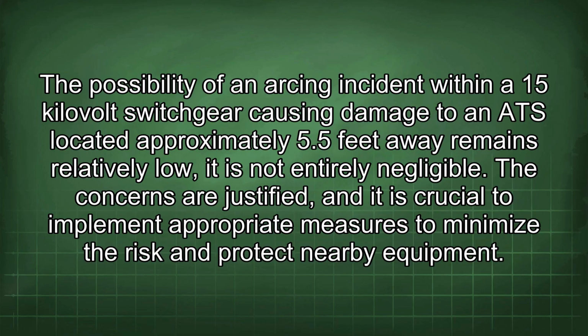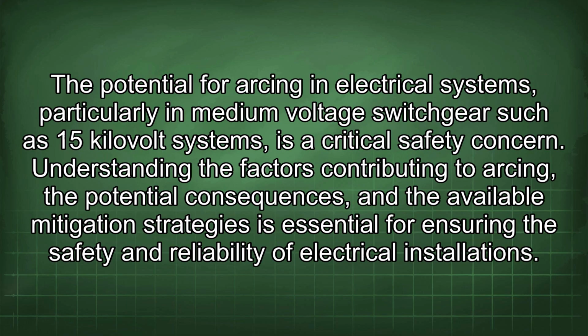The possibility of an arcing incident within a 15 kilovolt switchgear causing damage to an ATS located approximately 5.5 feet away remains relatively low. It is not entirely negligible. The concerns are justified, and it is crucial to implement appropriate measures to minimize the risk and protect nearby equipment. The potential for arcing in electrical systems, particularly in medium voltage switchgear such as 15 kilovolt systems, is a critical safety concern. Understanding the factors contributing to arcing, the potential consequences, and the available mitigation strategies is essential for ensuring the safety and reliability of electrical installations.